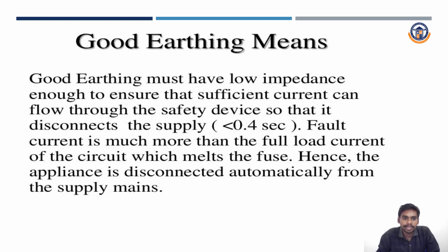Good earthing must have low impedance, enough to ensure that sufficient current can flow through the safety device so that it disconnects the supply within 0.4 seconds. Fault current is much more than the full load current of the circuit, which melts the fuse. Hence the appliance is disconnected automatically from the supply mains. Whenever a fault occurs, the fuse will melt and cut off the supply, separating the equipment.